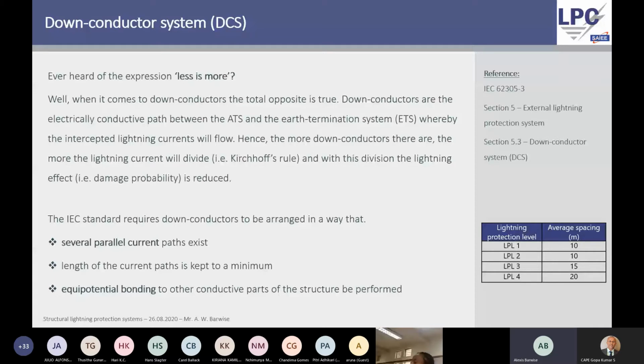So when we look at the IEC standard, it gives us 3 key things to consider. 1, several parallel current paths. So it indicates to us that at the very least there should be more than 1 down conductor, right? So we should have several. It tells us to keep the lengths to a minimum, and I'll explain that in the example.